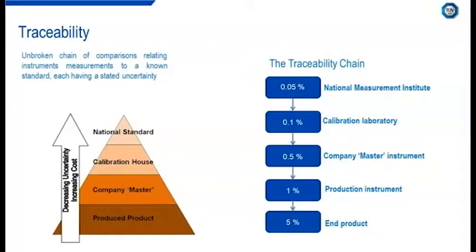The National Measurement Institutes and holders of the national standards provide the highest level of standards for the calibration and measurement traceability, and they sit at the top of the traceability chain. Each step of the calibration chain will have an uncertainty, becoming smaller at each step as we trace back to the national standards. Although the end product will be traceable to national standards, it's important to note that the uncertainty associated with the instrument will be significantly larger than the national standard laboratory.